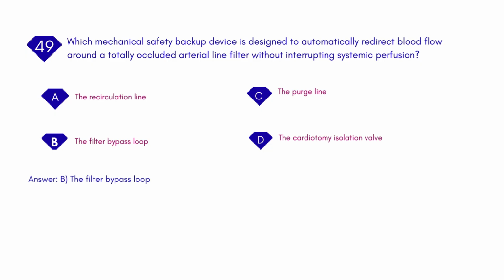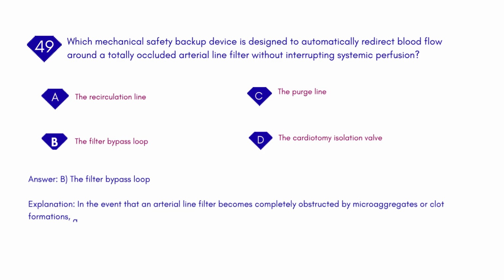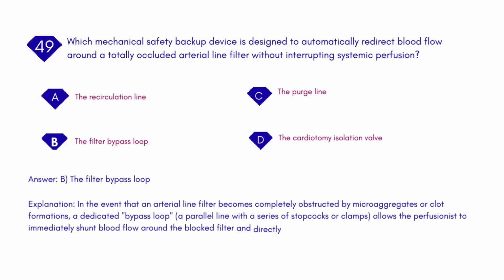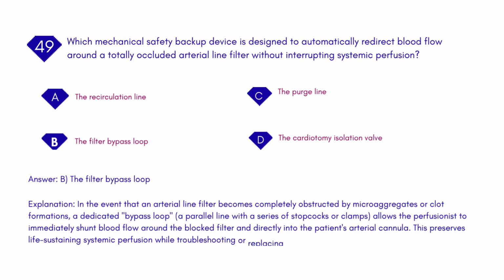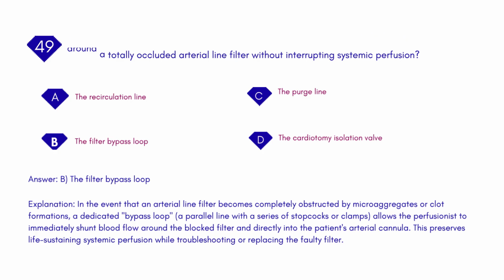The filter bypass loop. Explanation: in the event that an arterial line filter becomes completely obstructed by microaggregates or clot formations, a dedicated bypass loop, a parallel line with a series of stopcocks or clamps, allows the perfusionist to immediately shunt blood flow around the blocked filter and directly into the patient's arterial cannula. This preserves life-sustaining systemic perfusion while troubleshooting or replacing the faulty filter.